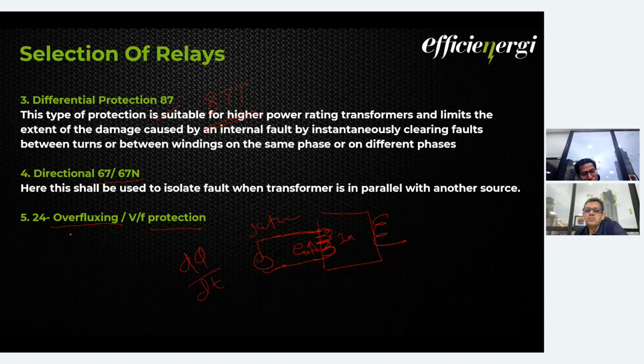Now, because of the overfluxing, this d phi by dt becomes almost zero, not zero, but close to zero. So there is no back EMF. Now the voltage goes directly across the resistance of the winding, because there is no back EMF to restrict the current. So heavy inrush current or heavy current will flow and the winding will get damaged. To avoid this, 24 is installed. For a bigger transformer we are doing this. For a smaller transformer, we are not using overfluxing protection.